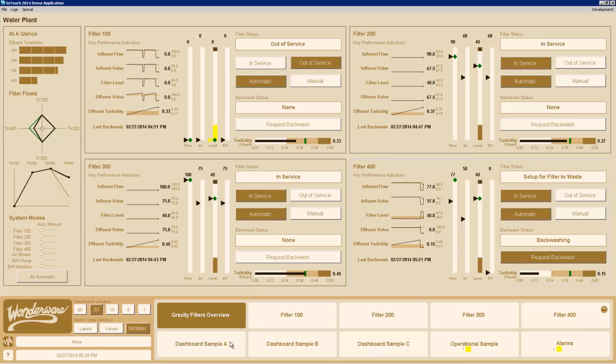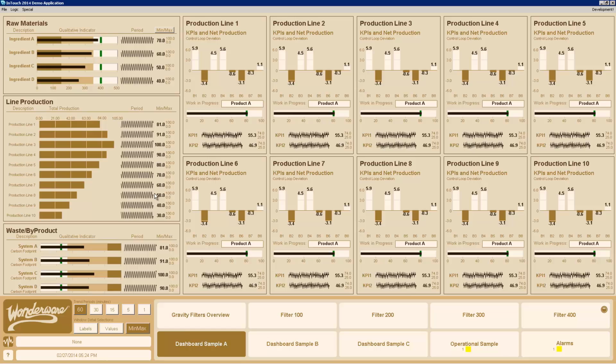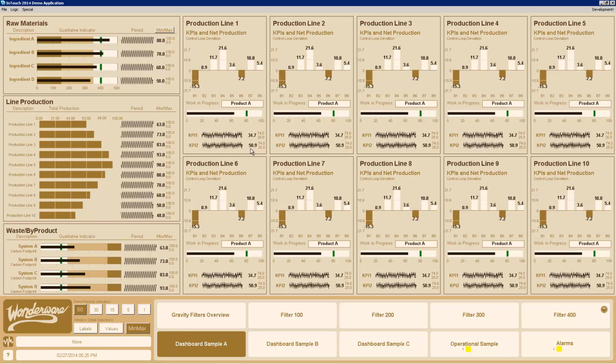Now I'm going to switch over to yet another process graphic where I've doubled the number of trends again, to I think 38 trends. If I pull up even an hour's data, you can see that the noise is coming in. There's a lot of noise in that, but it performs very quickly. We have tested this up to 200 trends on a single graphic and still not seen any major degradation in overall draw performance from what you would have with just normal graphic elements on the screen.